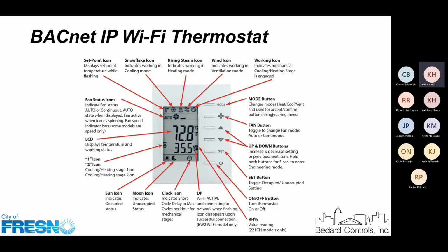The mode button is important. It allows the change between heating, cooling, and ventilation. We've automated that, so it'll change between heating and cooling depending on what temperature it senses. The fan button's the same way. In your application, the supply fan is always running when occupied because it's a commercial space.